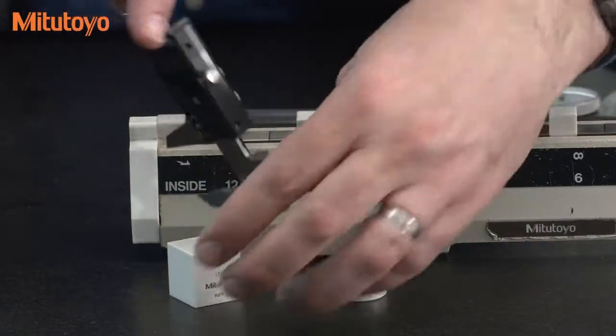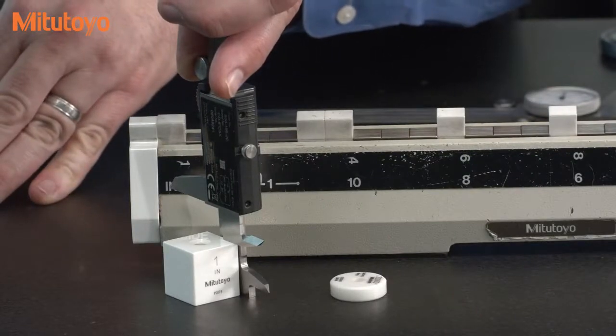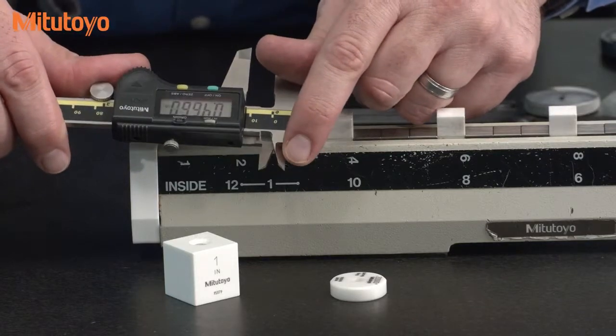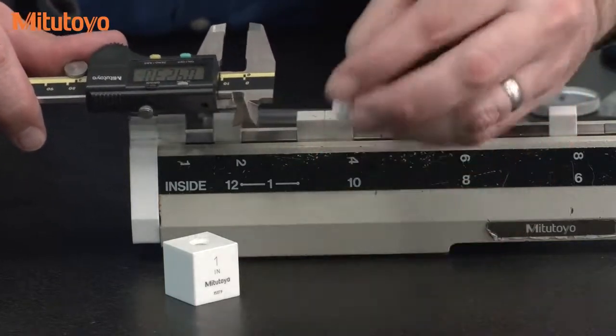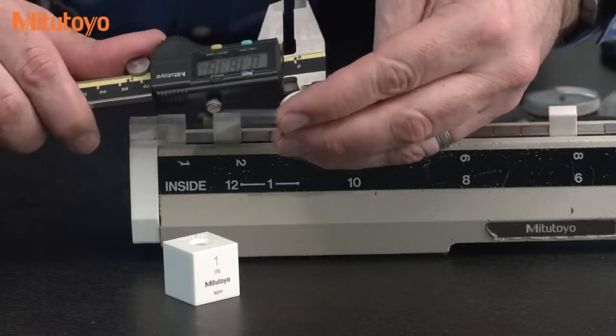This caliper has a step function so we do a measurement like that, and then to make sure that we don't have any problems with the small inside knife edges, we measure a two hundred thousandths ring gauge like that.